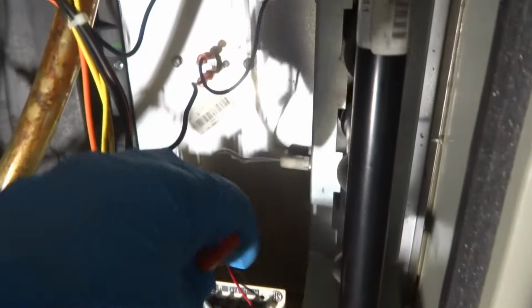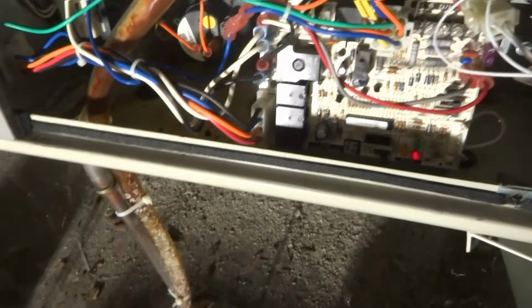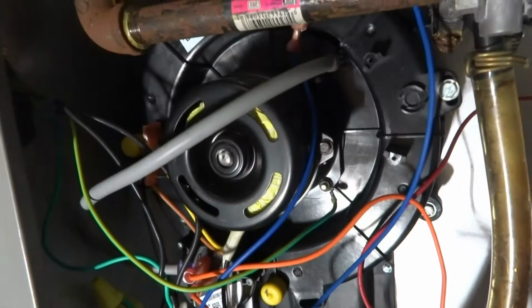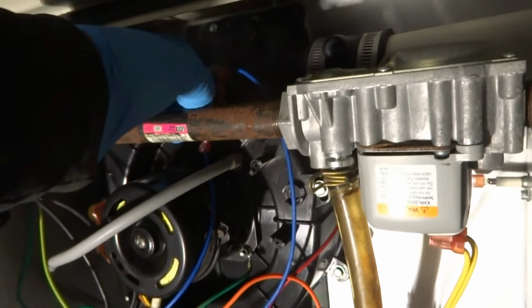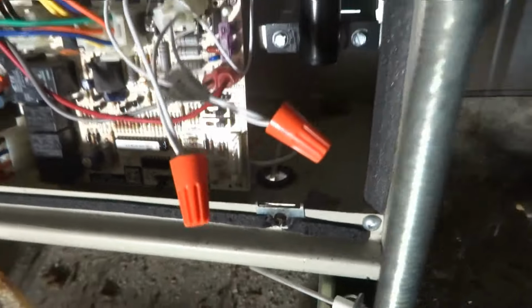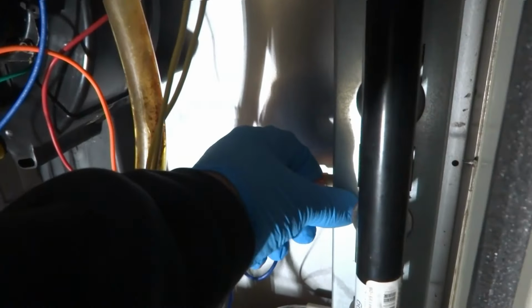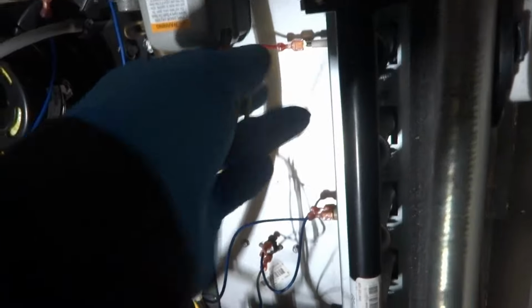Well, let's see, got one of them weird igniters. Was it giving off any codes? You did vacuum that? I did vacuum those two, yep. Pulled them out, vacuumed them. I changed the filter, even though it didn't look like it needed to be changed. Don't look like we're getting any glow there. What's weird is before it was dropping, what is it, out of those two hoses right in the beginning. It doesn't seem like it's doing that anymore.